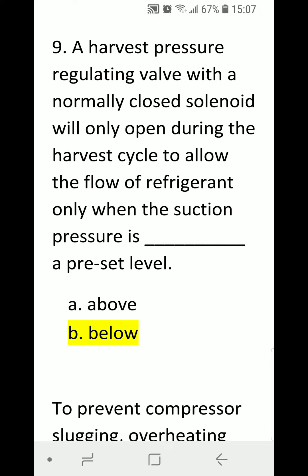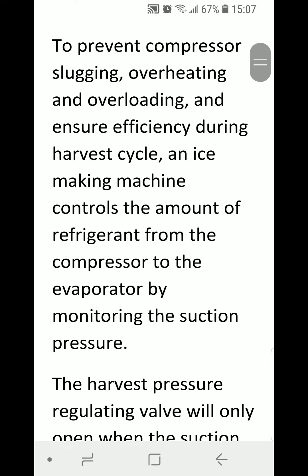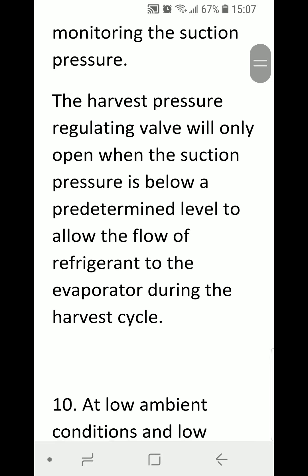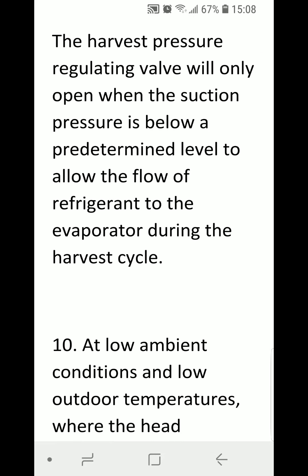Number nine: a harvest pressure regulating valve with a normally closed solenoid will only open during the harvest cycle to allow the flow of refrigerant only when the suction pressure is blank a preset level. A) above, B) below. Correct answer is B, below — to prevent compressor slugging, overheating, and overloading. The harvest pressure regulating valve will only open when suction pressure is below a predetermined level to allow refrigerant flow to the evaporator during the harvest cycle.